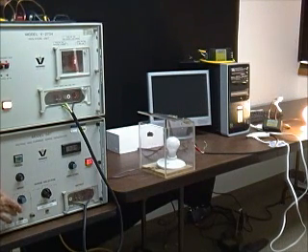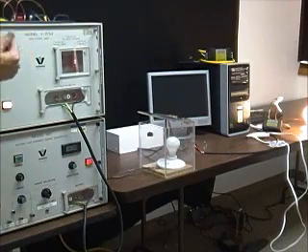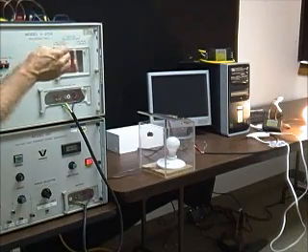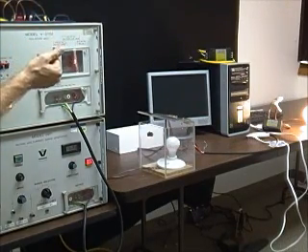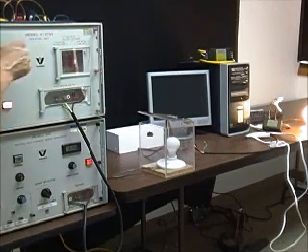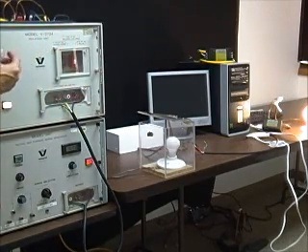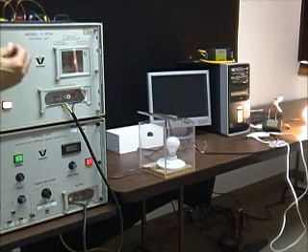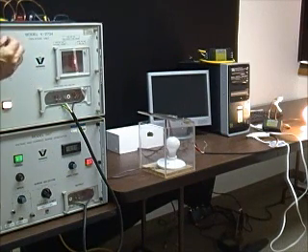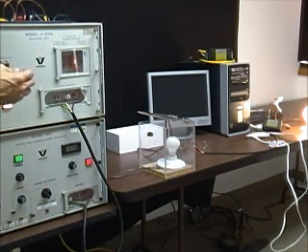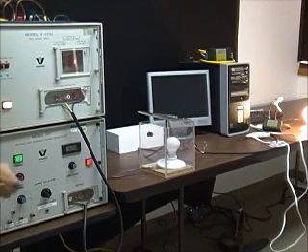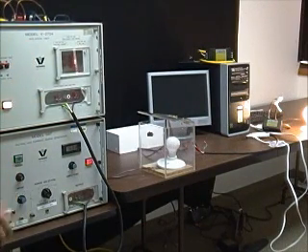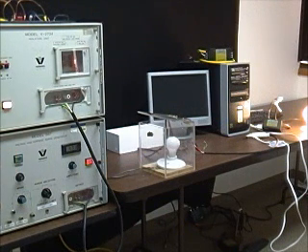So what we see here is that the farther away the surge suppressor is from the load, the less positive impact is going to be had for the first level of equipment. So the necessity is to go ahead and have a cascade approach in all of your electronic cabinets, your control cabinets. This will provide the optimal level of protection for all of your electronic equipment. Thank you.